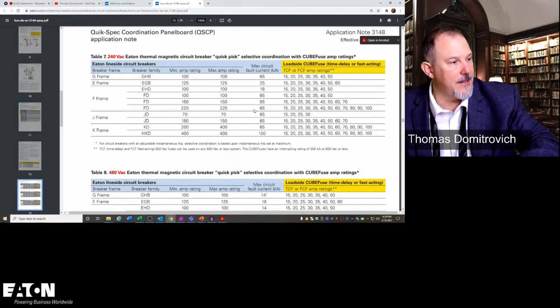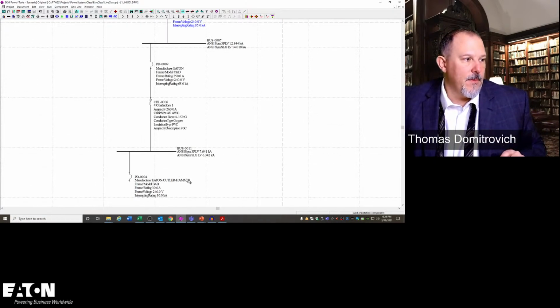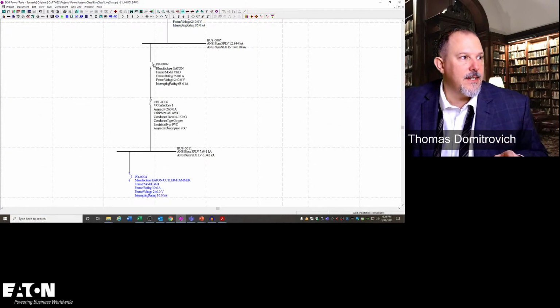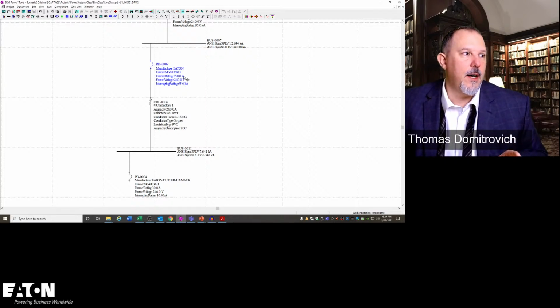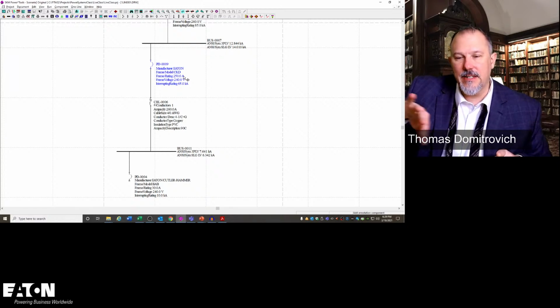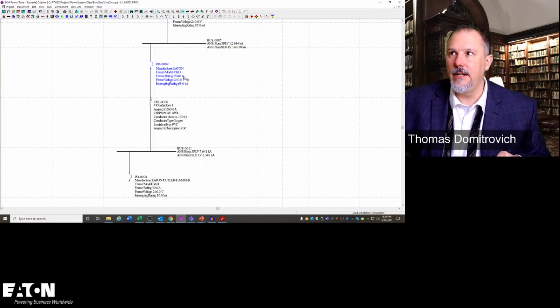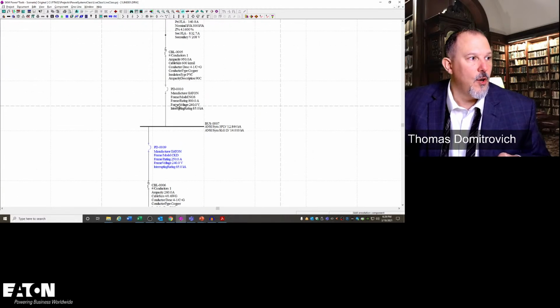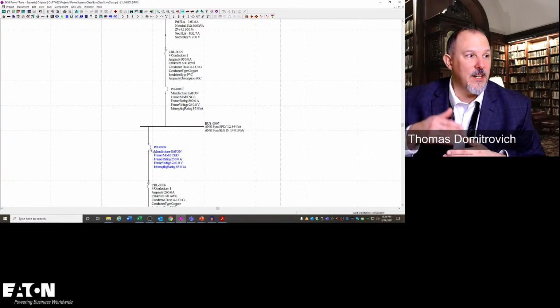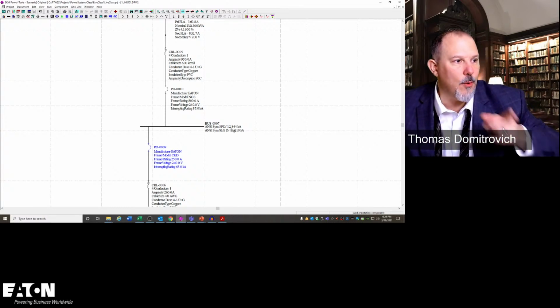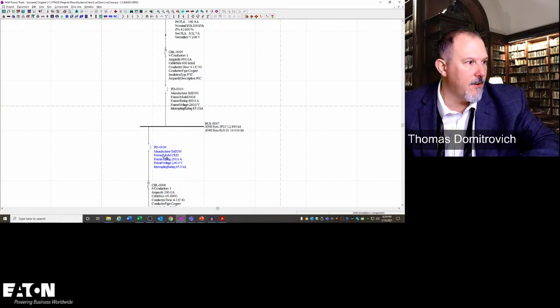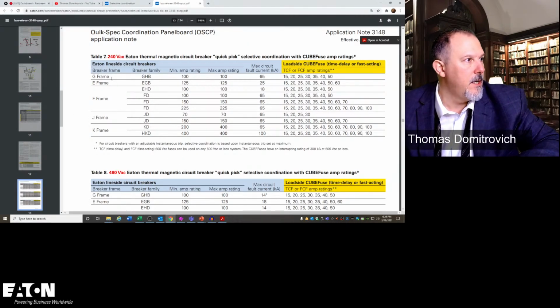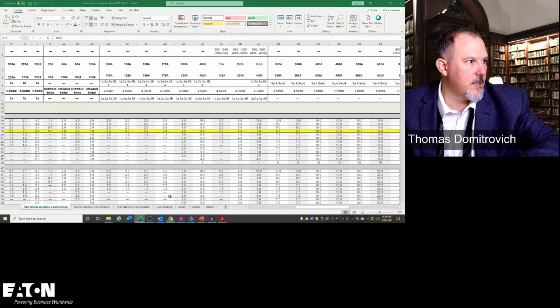And here's what that does. If this was a fuse, and this, instead of being an electronic trip unit, was a 250 amp breaker with a higher instantaneous pickup, remember, I need to selectively coordinate this breaker with this one. So the bigger that one is, the harder it's going to be for me to selectively coordinate. So let's look at this one. This is 12,844. I've got an 800 amp. I'm starting with a CKD. So let's go back to my table, CKD.